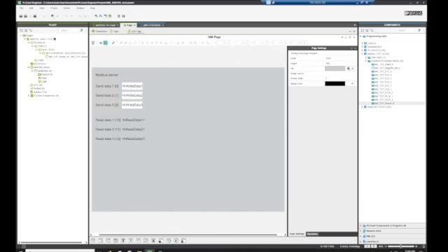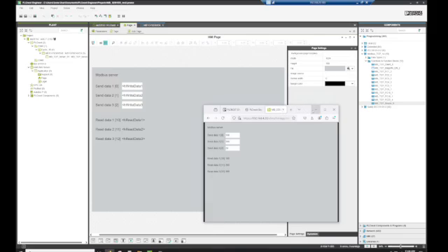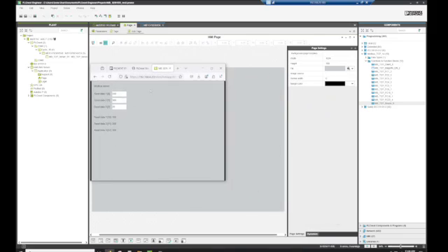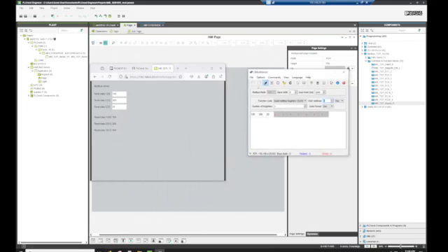So now that we've looked at this a little bit, let's go ahead and pull that piece up. Here is the web page running inside the PLC Next. Here is QModMaster, which I'm using to just poll the device. If you'll notice, we are already connected to this block because I've been playing with it. If we go ahead and change some of the data, you'll see we have 100, 320, and we're reading the holding registers. So that's going to be this data, 100, 320, and that's the Modbus server sending that data out, and then we're reading it. So if this is 25, and this is 50, and this is 75, and then we go ahead and do a read, you'll notice that all of our values have changed to match what the server is sending us.